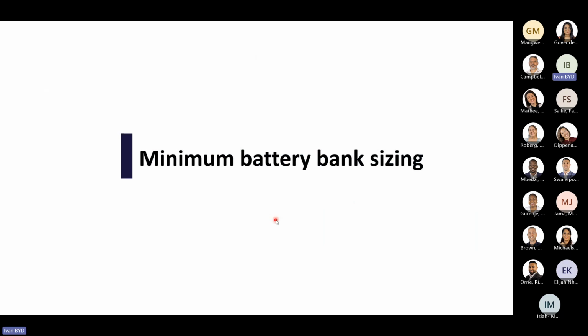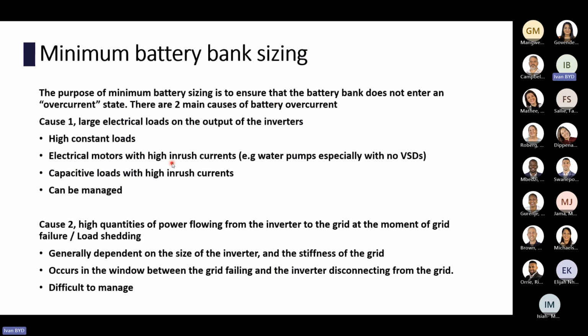So minimum battery bank sizing. One of the big reasons why you need a minimum battery bank size is, one, you've got inrush currents on your loads, but you can control those. So supposing you've got a motor and your motor has inrush currents, but if you don't have motors, or other inductive and capacitive loads, you won't necessarily have inrush currents. So you'd be able to size the bank according to your loads.